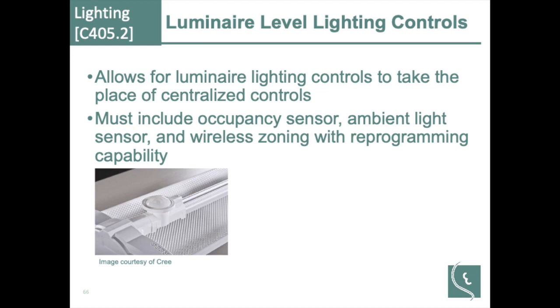In order to qualify as luminaire level lighting controls, say that 3 times fast, not only does it have to do occupancy sensing, ambient light or daylight harvesting, but also wireless zoning and reprogramming capabilities. So there's a fair bit of capability required.